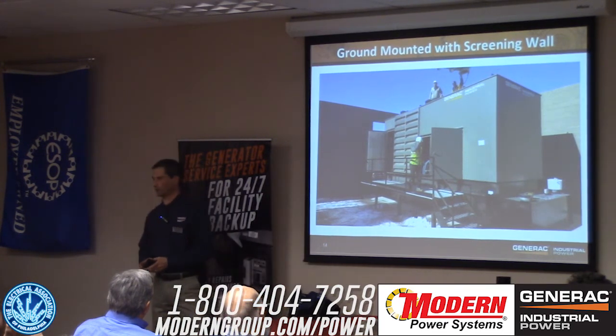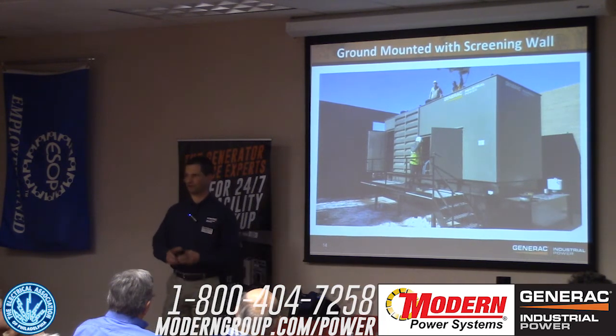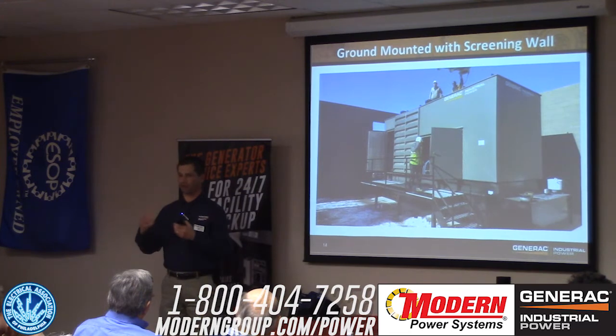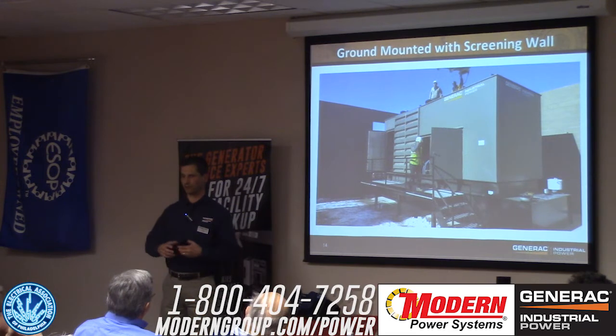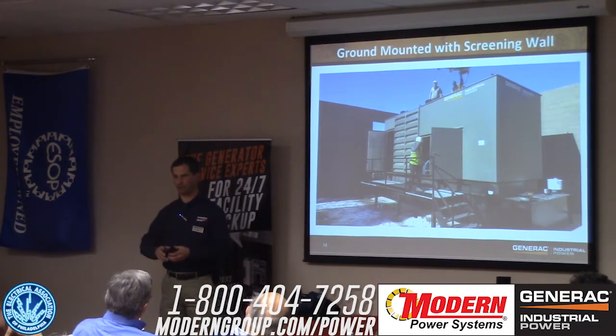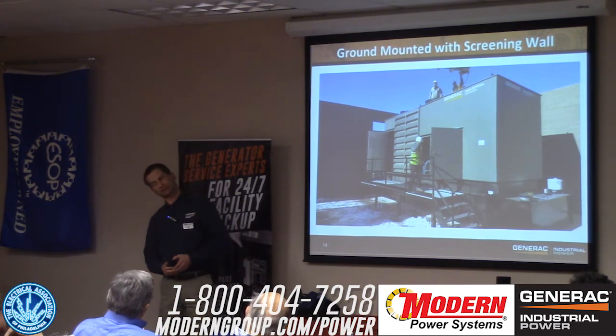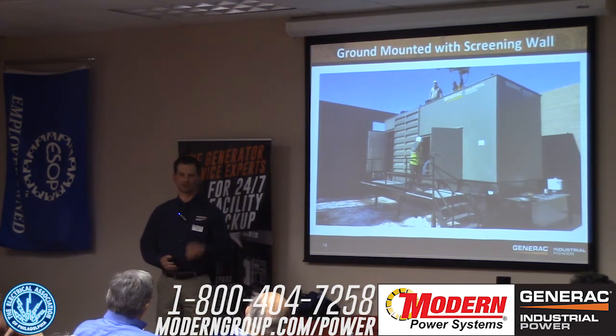Keep in mind one of the standards for base fuel tanks—has anybody heard of UL 142? Diesel base tanks or above ground storage tanks—that's the standard. Just be aware that in some locations they have their own requirements over and above that. So if you go in with a bone stock UL 142 tank thinking you're all good, you might miss monitoring requirements.